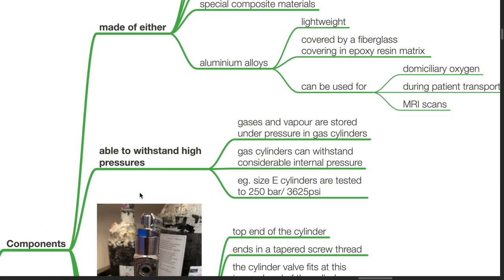Gas cylinders are able to withstand high pressures. Gases and vapors are stored under pressure in gas cylinders. Gas cylinders can withstand considerable internal pressures. For example, size E cylinders are tested to 250 bar or 3625 psi.